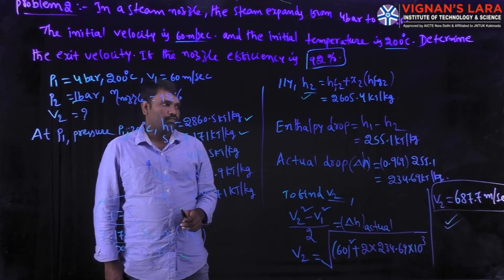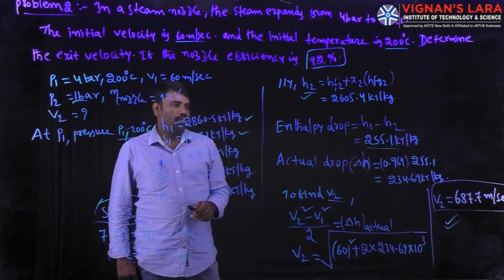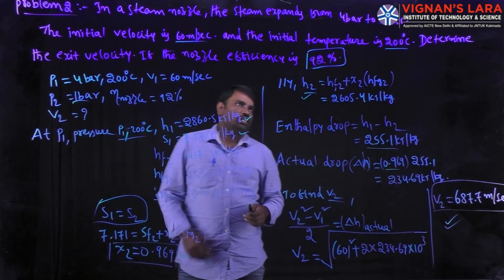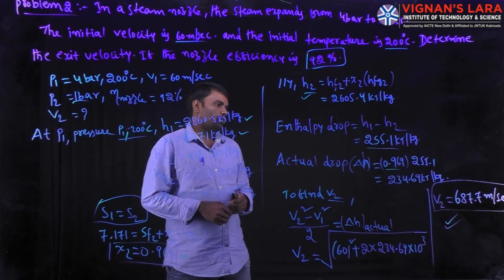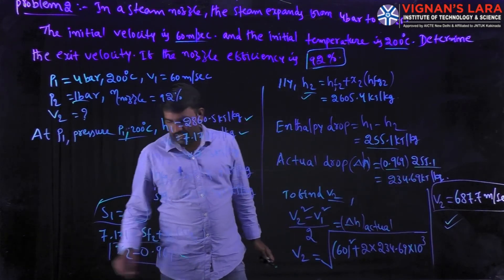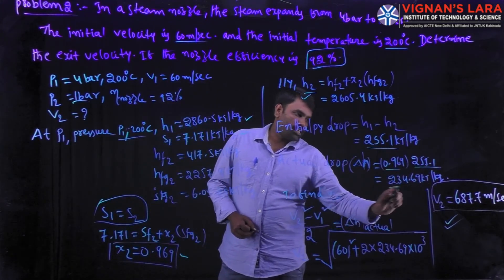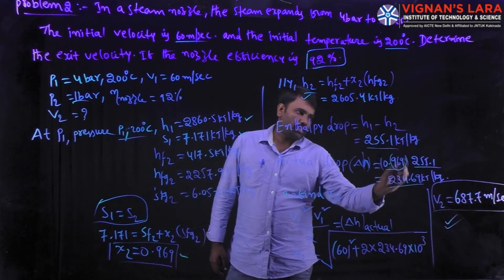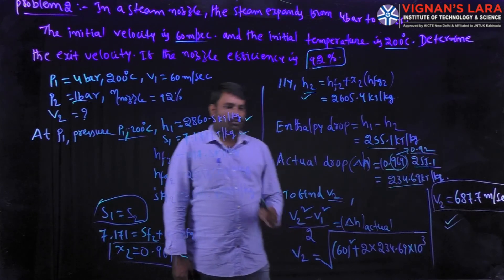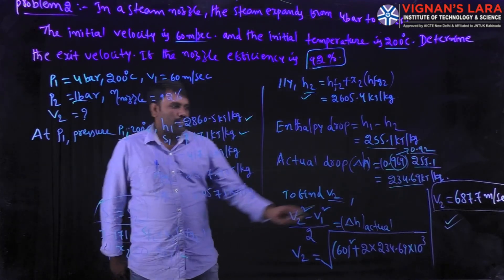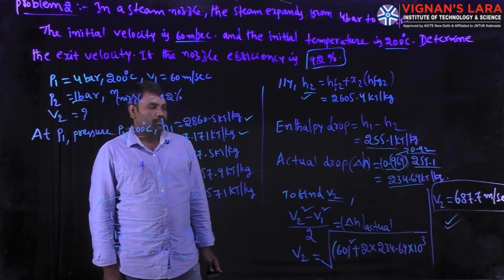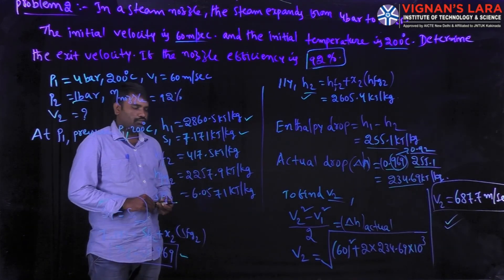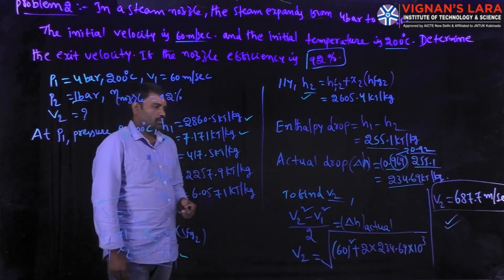After finding h2, the theoretical enthalpy drop is h1 minus h2, which can be easily calculated. The actual enthalpy drop is then found by multiplying the nozzle efficiency — 0.92 — by the theoretical enthalpy drop. So the actual enthalpy drop equals 0.92 times the theoretical value. After calculating the actual enthalpy drop, you can determine the actual exit velocity of the steam.